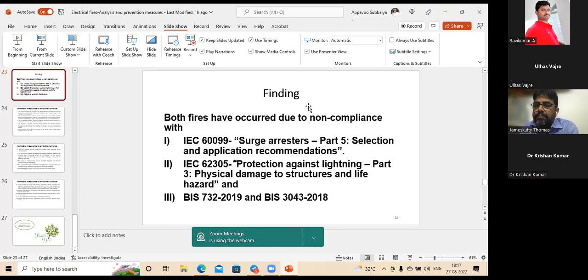Yes. See, in this specific case study, I wanted to eliminate all the possible causes of incendiary fire and all the possible causes of lightning fire. We can only establish that our probability is tending more towards the lightning. In both the buildings, after the solar panel erection, they have provided an ESE type arrestor. I have said that this ESE type arrestor, once installed in a monumental ancient temple building, a 1,200-year-old temple, some parts got damaged during the lightning. We had protected the building for the past 1,200 years. Similarly, in this case, we can't take a risk, being a commercial establishment with crores of worth of material inside the process plant.